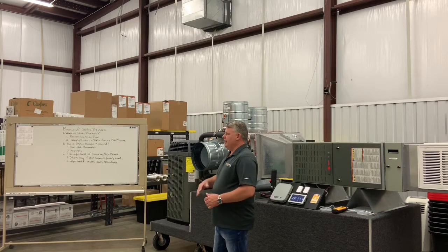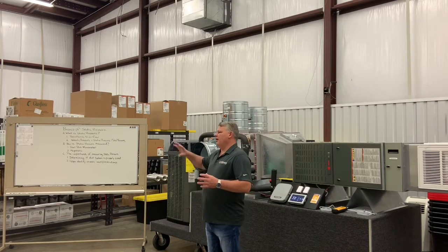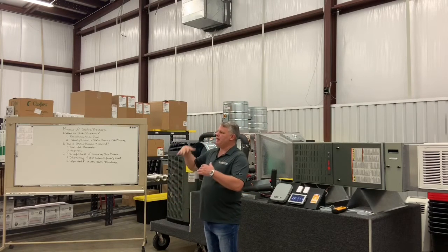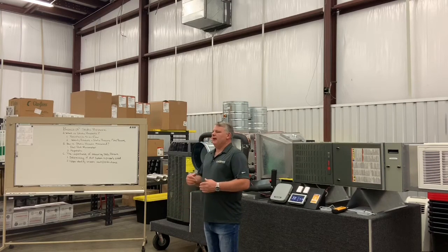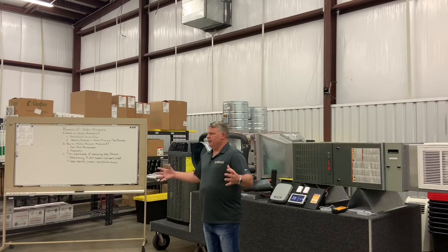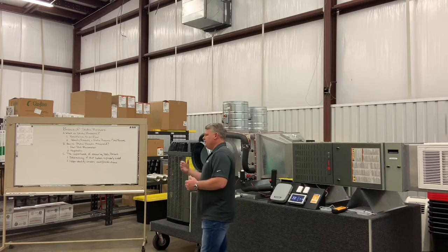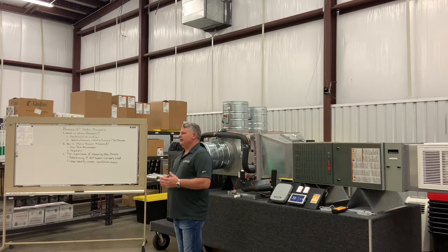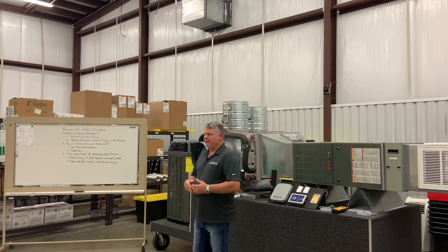But when you get into a two-story house where there's long extended duct runs going from the top attic into the side attic or down into the first story, these duct systems begin to build up a lot of resistance. And so there's two types of pressure in a duct system. We have velocity pressure and we have static pressure.